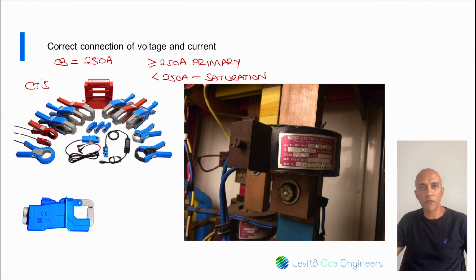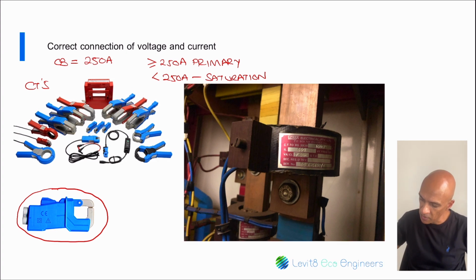Now, depending on the type of instrument you are using, the secondary of the current transformer may be 5 amps, or the CT may be a transducer which outputs a certain voltage as a secondary current. I use an instrument that has a 5 amp 1 volt transducer. So this transducer is meant to clip onto an existing panel CT and uses the secondary current of the CT, the 5 amp side, and converts that to 1 volt. The instrument software then interprets the voltage received and displays it back as a current. So here's a photo of the typical transducer that I use, which is 5 amp 1 volt.